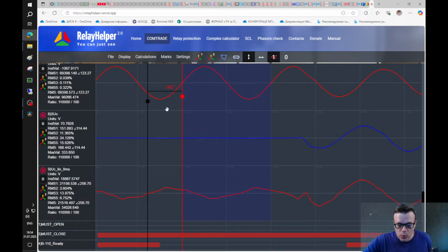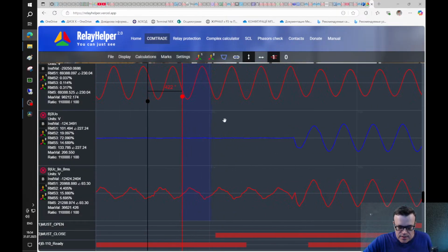So why was that? The problem was that this function has an algorithm that determines that the line is dead. Usually this term is used. If the voltage on the protected object is below some value, the protection determines that the object is without voltage, so it's dead, and at this point the automatic reclosing function can proceed.